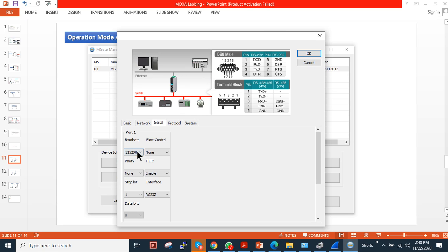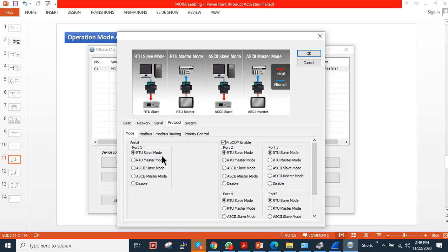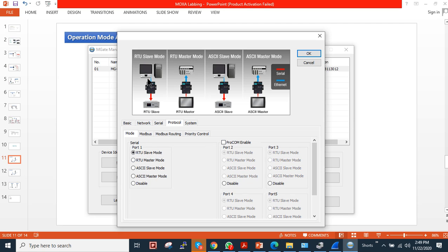Serial side - we will configure the parameters as 115200, flow none, parity none, FIFO enable, stop bit one, and interface. As you can see, it's software selectable so you can choose according to your requirement. In my case, I am using RS-485 two wire, so I will choose two wire. Under the protocol, I will disable this PROCOM.